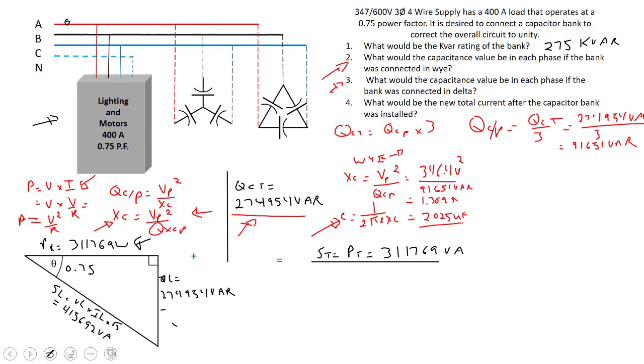Now if I were to do this in delta and figure out what size each capacitor would have to be, I'm going to do the exact same step. The only difference is my phase voltage is now different. XC in delta would be V phase squared divided by QXC in the phase. Now our phase voltage is the same as line voltage, 600 volt squared divided by our 91,651 VAR. That's about 3.928 ohms of capacitive reactance.